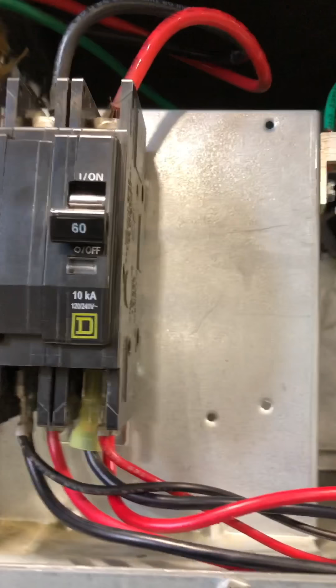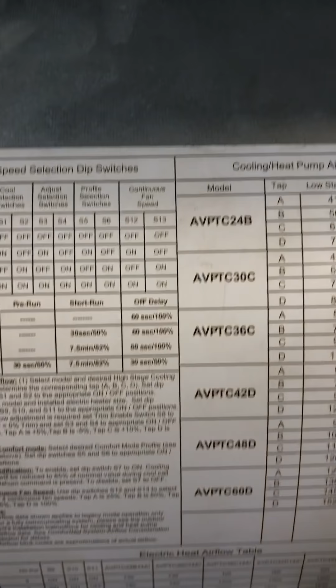I think we're all familiar with this. This is just a breaker. It's a 60 amp breaker. The reason this is a 60 amp breaker is because when these heating elements are running, they're going to run roughly about 20 amps apiece. So if we have two elements plus a blower motor, we're going to be running about 45 amps. We only want to use 80% of our circuit, so we need about 25% more capacity. So we have the 60 on here. But if we have a short circuit situation, which we'll learn about, this will pop and cut the power off.